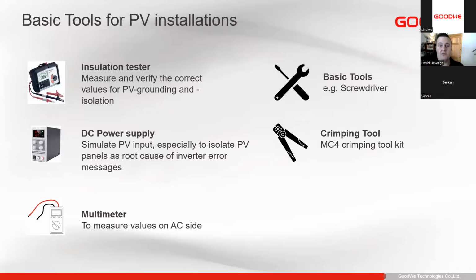These are some of the typical tools you'll use for fault finding. An insulation resistance tester is always a good tool to have for a PV installer. That way we can make sure that the resistance from our strings to ground is sufficient. The way that works is it injects either 600 or 1000 volts into those cables, and then you can see whether any of that voltage is leaking to ground. So when we have isolation faults or anything like that, an insulation resistance tester is needed to test that. And if you have basic tools, a DC power supply, which is not vital for a hybrid, but it is much more convenient when you are doing on-grids, your general crimping tools, and a multimeter.